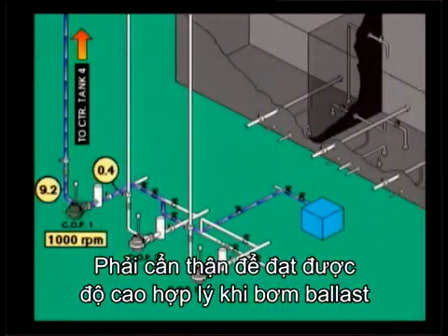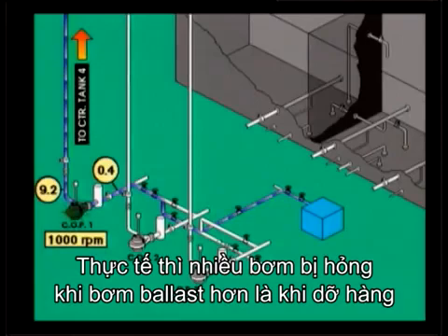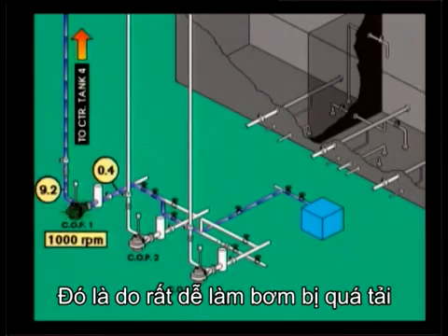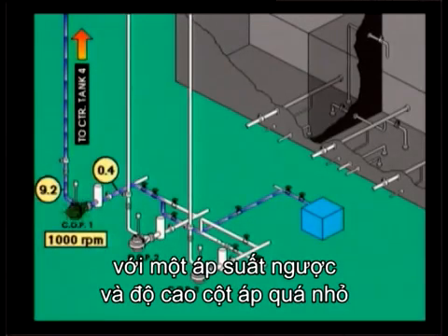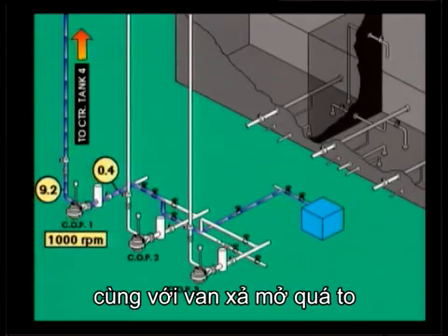Be careful to obtain a suitable head while pumping ballast. Possibly more pumps have been damaged during ballasting than during discharge. This is because it is so easy to run the pump in overcapacity with too small a back pressure and head, with the discharge valve wide open.